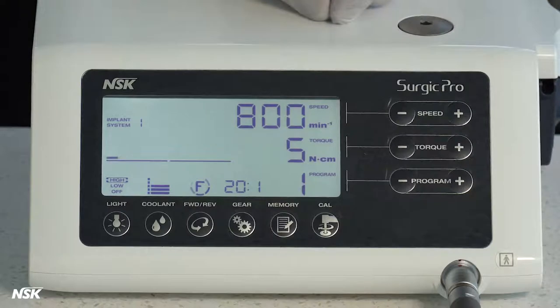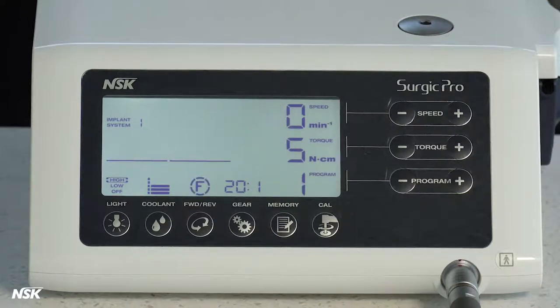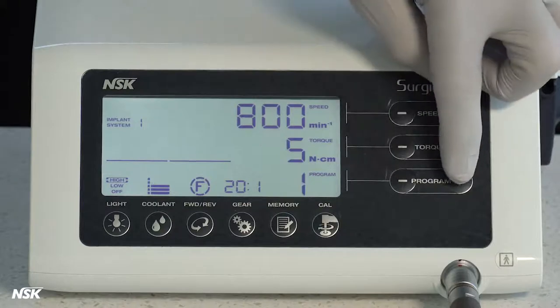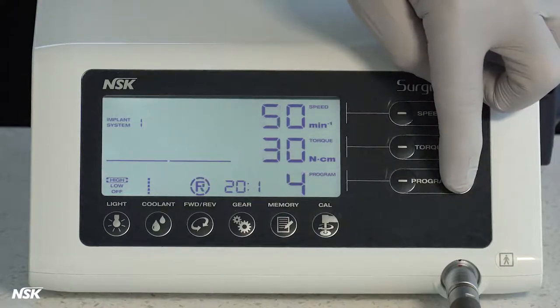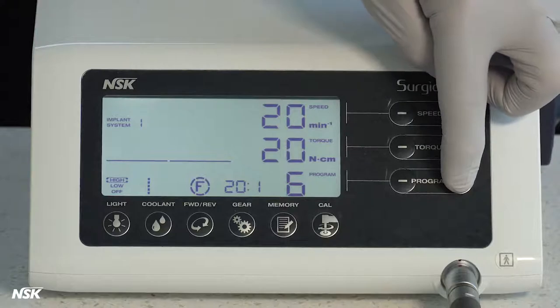Torque buttons are used to change or set the torque values between 5 and 80 Newton centimeters for implant attachments. You will notice the amount of bone resistance applied to the drill is displayed here like a graph during operation. Program buttons will select any of eight programs in each of eight implant systems.